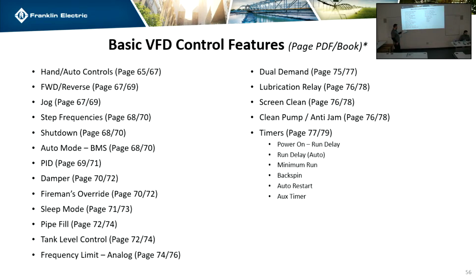Shutdown, basically, you have an input. If you set it to shutdown, anytime it sees a signal, it's going to shut the drive down. You can flop it between normally open and normally closed, and the two control options are automatic restart or not automatic restart. I believe if you're setting it up from a spec for a fire code, the code's going to tell you not to automatically restart it. They're going to want someone to physically reset it, but both options are there if you need it.